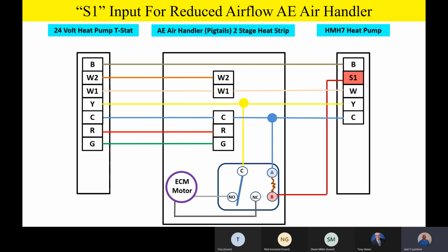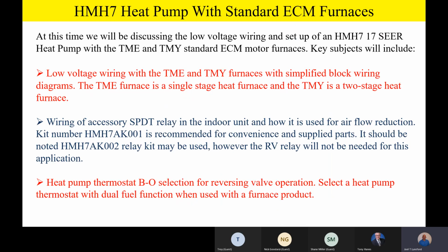Okay. Well, team, the next thing we're going to talk about is utilizing the HMH heat pump in a dual fuel application with a standard ECM furnace. And so basically you're going to notice that the block wiring diagram is going to be very, very similar to what we just talked about, but we're going to literally go over it wire for wire, for both single stage and 2-stage heat pump, single stage and 2-stage furnaces with our HMH heat pump. Now we're going to continue to use that wiring accessory, that single pole double throw relay in the indoor unit for airflow reduction. And again, that kit number 001 is going to be recommended for convenience and supplied parts.